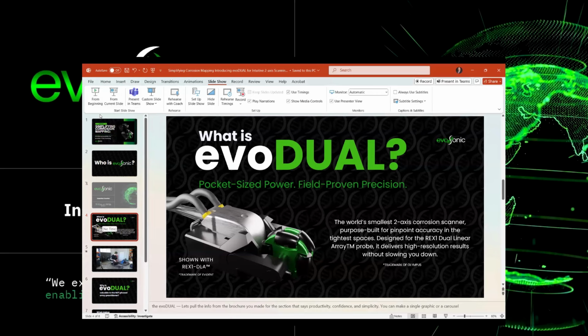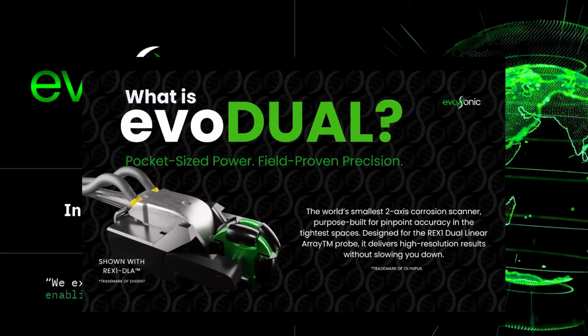So this product combines all the benefits of the Evo ARC, as it's built into the scanner for the circumferential contactless encoding, and it combines it with the near surface resolution of the REX1 DLA. And then we're tracking the axial distance with that Omni wheel on the front. So we're giving the techs a two-dimensional encoding on the horizontal piping assets of various diameters and sizings. I just wanted to hit that note that this is for horizontal piping up to 70 degrees from horizontal.